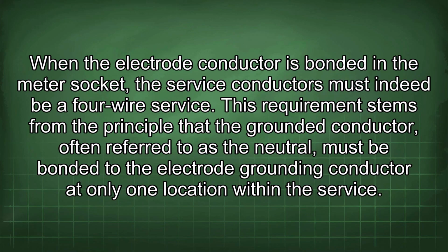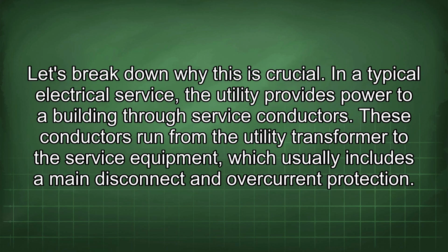When the electrode conductor is bonded in the meter socket, the service conductors must indeed be a 4-wire service. This requirement stems from the principle that the grounded conductor, often referred to as the neutral, must be bonded to the electrode grounding conductor at only one location within the service. Let's break down why this is crucial.